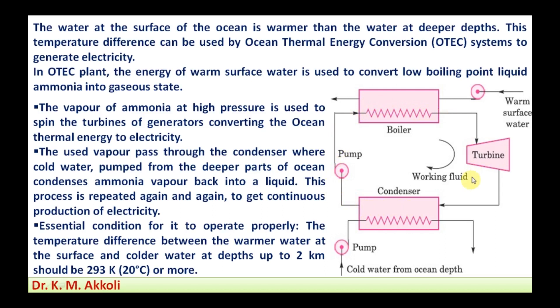The liquid ammonia is supplied again by pump to the boiler, and this cycle continues for continuous generation of electricity. The used warm surface water as well as the cold deep water are pumped back to the sea. The required temperature difference for operation of this system is around 20 to 25 degrees Celsius.